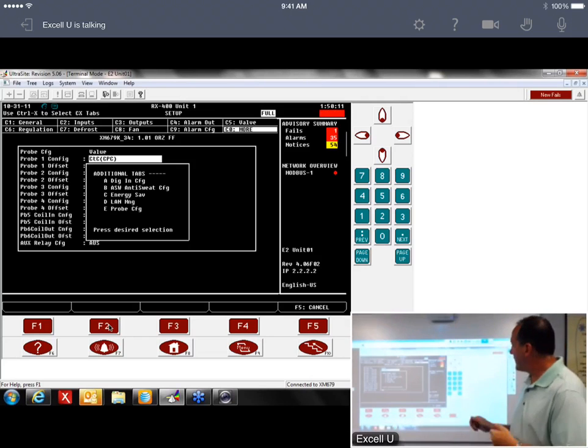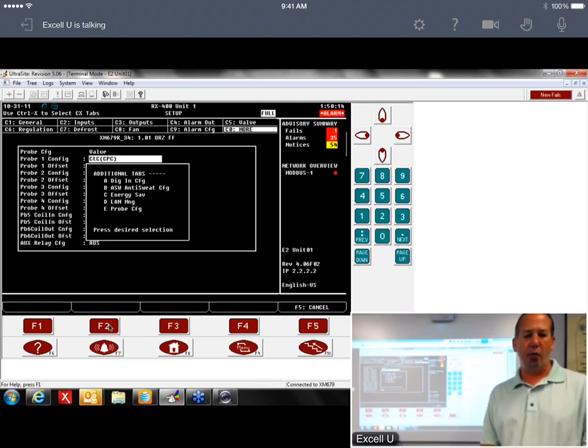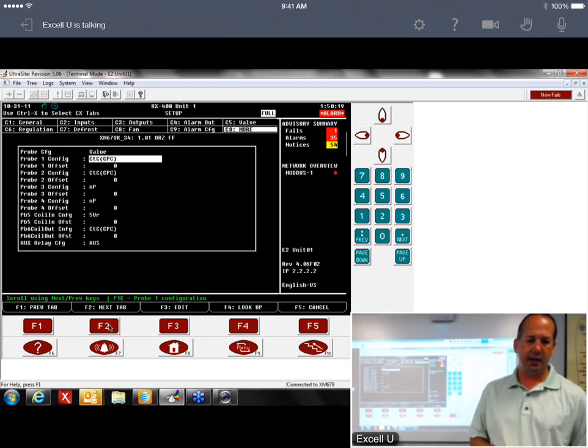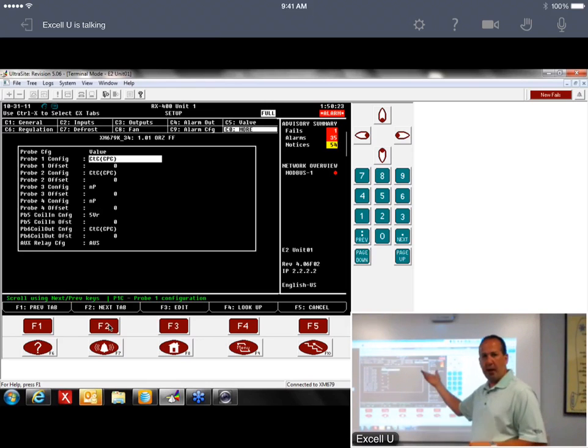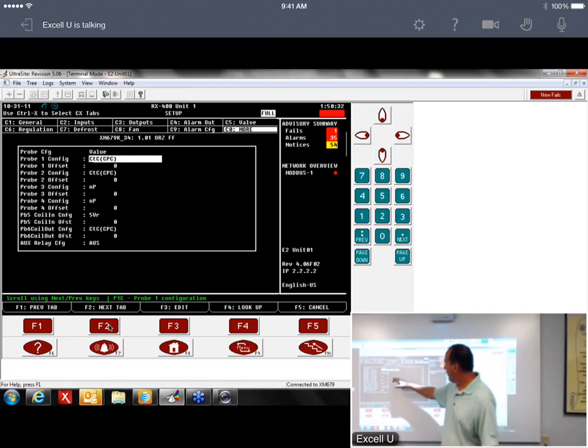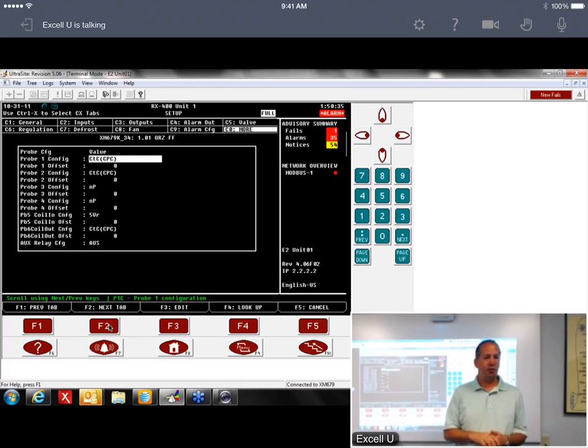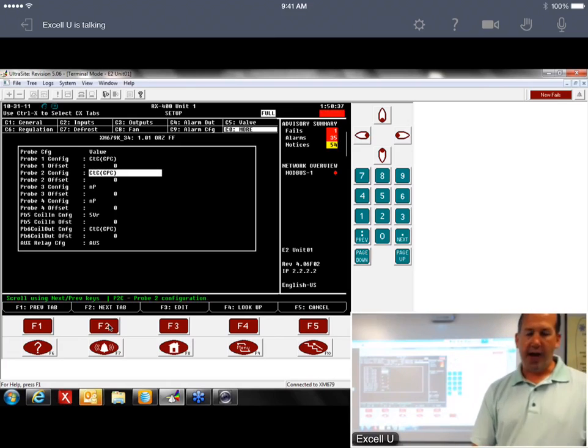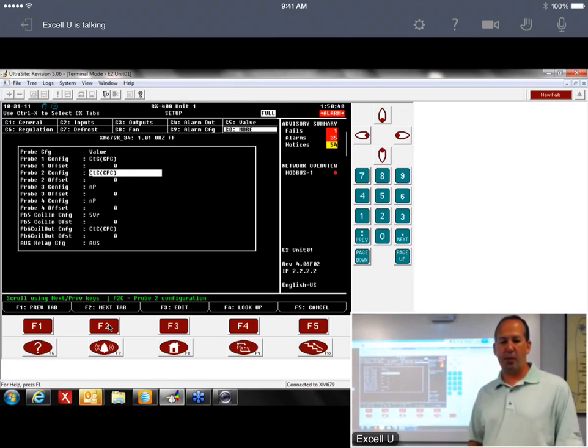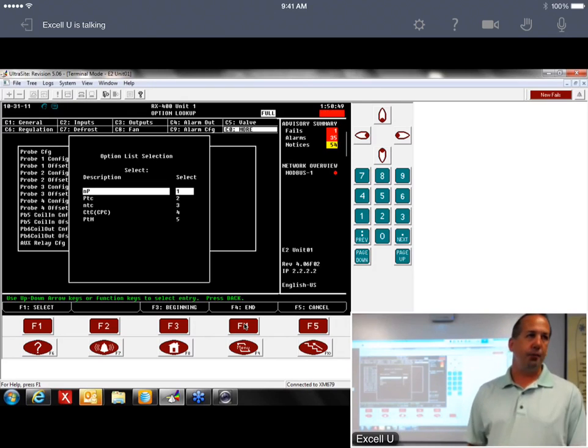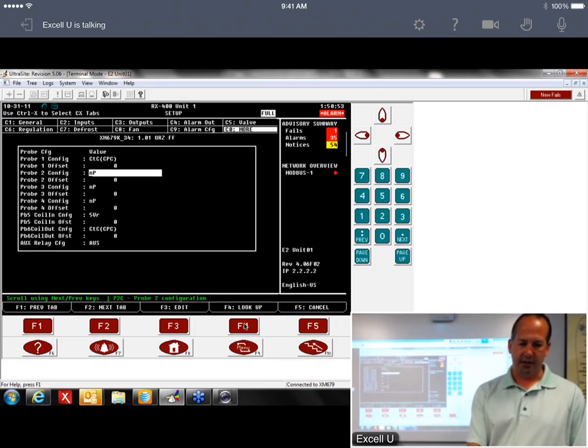So again, I hit C0 for the More tab and the XM device setup, and we're going to go down here to E probe config. This is where we tell it what type of probes we've got. Now, the E2 by default is going to default every one of these probes to a CPC probe. 3 and 4 we don't use, so I set those to NP, which stands for no probe. If you had an off-cycle defrost case that didn't use a defrost termination, you'd also want to do the same thing to probe 2, defrost termination. So if I hit F4 lookup, NP's on the top. So I would set NP there. Actually, I want to change that one back though.